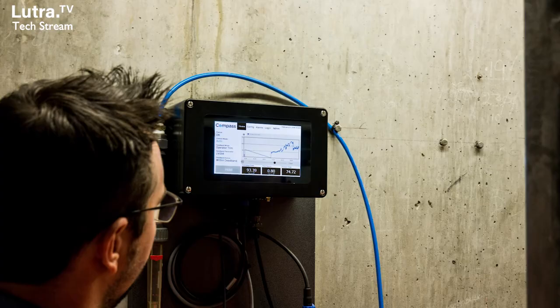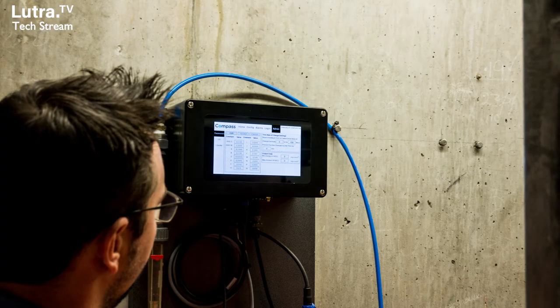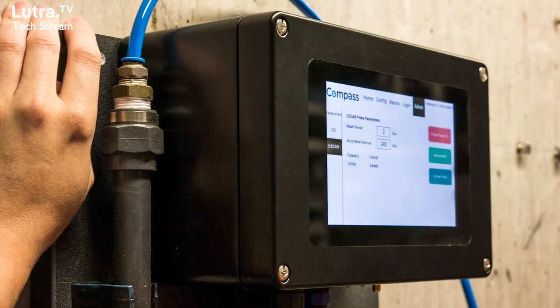One of the uses we've developed here at LUTRA is our Compass coagulant controller, which we use on water and wastewater treatment plants. At water plants, we're measuring the organics in the water and together with turbidity we come up with a coagulant dose. At wastewater plants, we developed a surrogate for phosphorus, which can be used at the back end of the plant to polish the final effluent before it gets discharged. The advantage is you can react much quicker to changes — ramping your chemical dose up or down as needed.